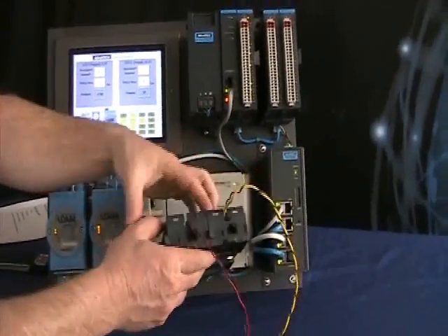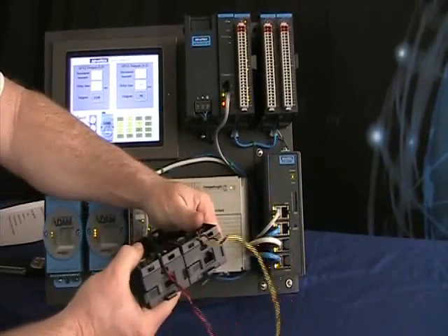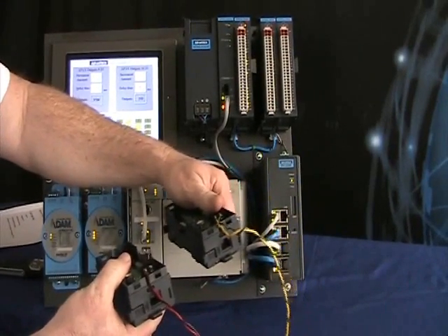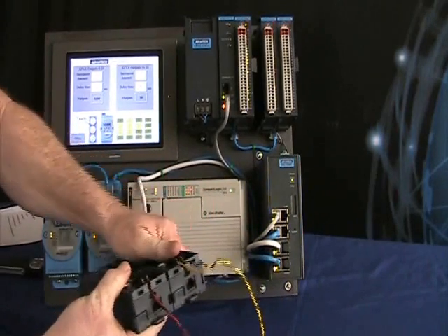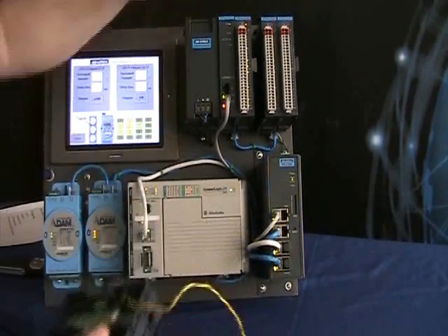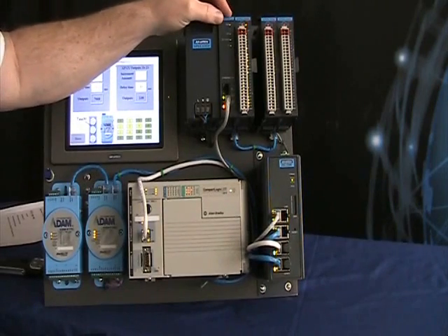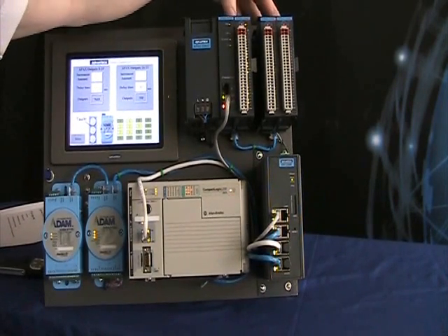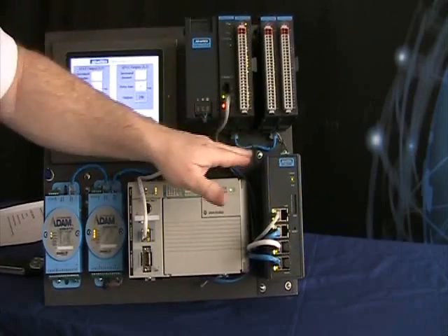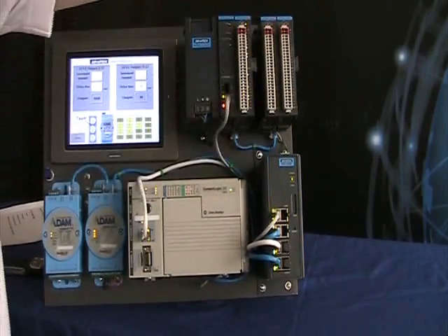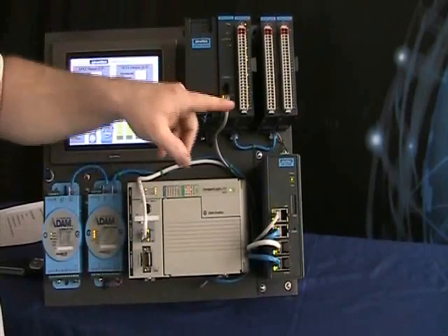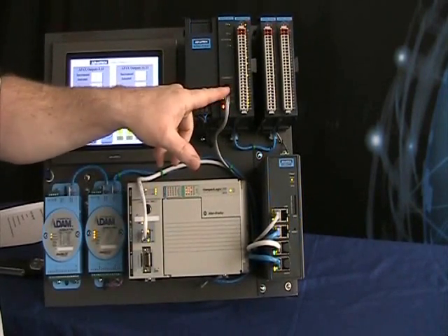Now when I talked about having the two separate Ethernet ports, this in itself lends it to having remote I.O. capabilities. So if you added this to your system, then this coupler would really be the only coupler you needed, and then it can have some on the backplane and then others, as you see the connector below, can be remotely mounted. But your controller only has to be connected to one coupler.